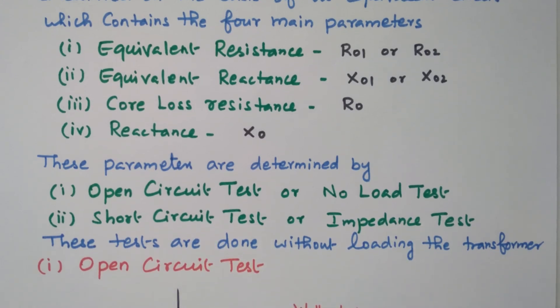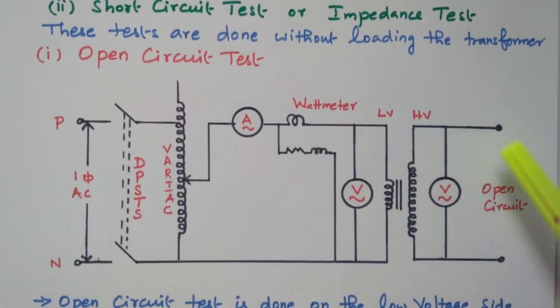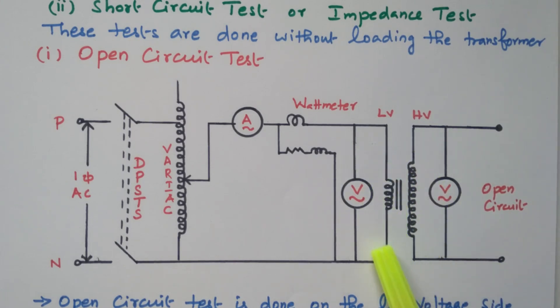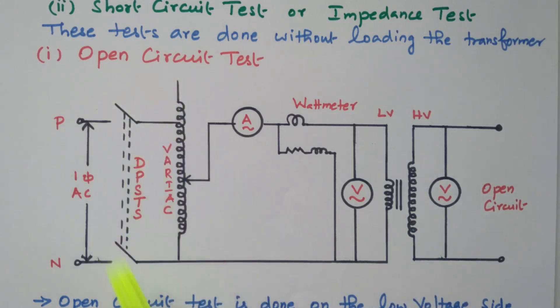In this video we will see the open circuit test. The open circuit means the secondary of the transformer is kept open — there is no load connected on the secondary side. Consider this transformer: this is the primary winding, this is the secondary winding. This is a low voltage winding, and the no load test is always performed on the low voltage winding. The high voltage winding is kept open.